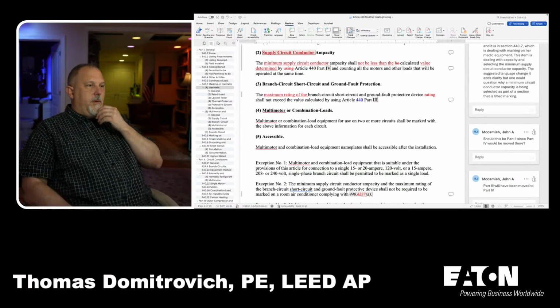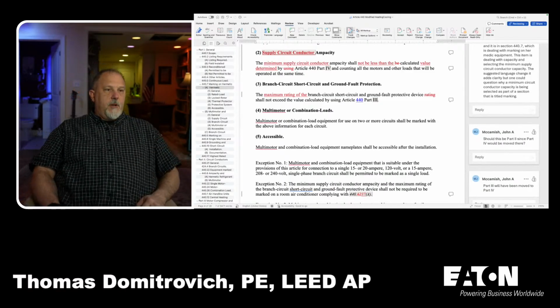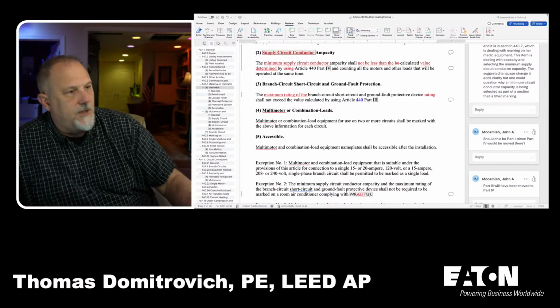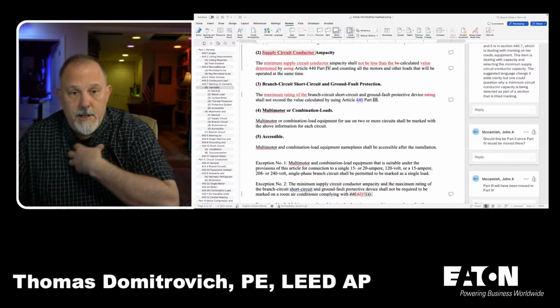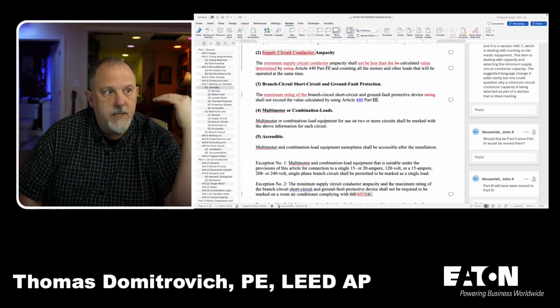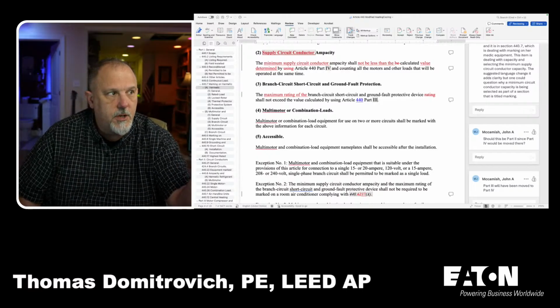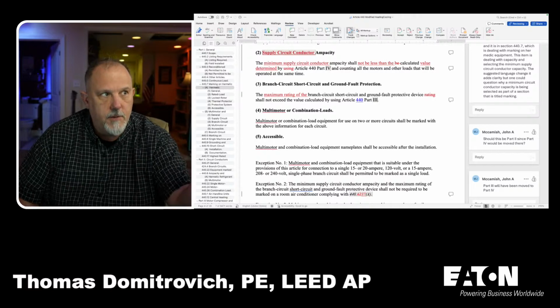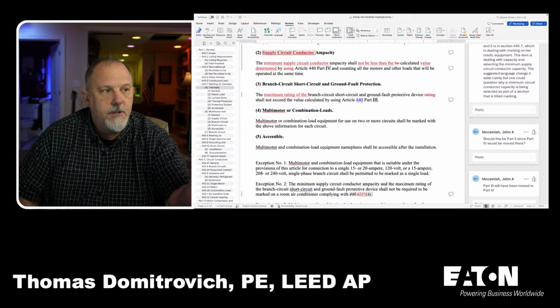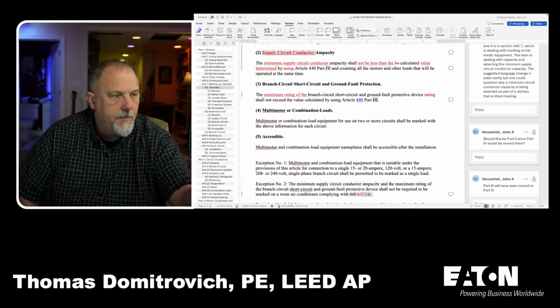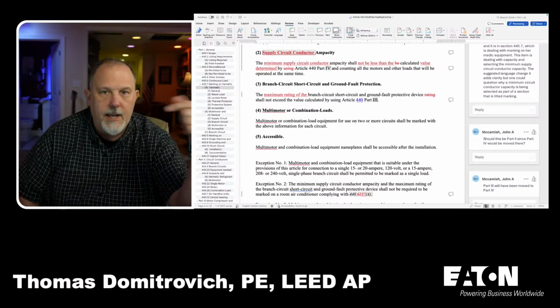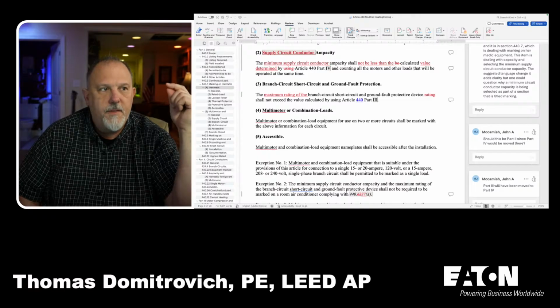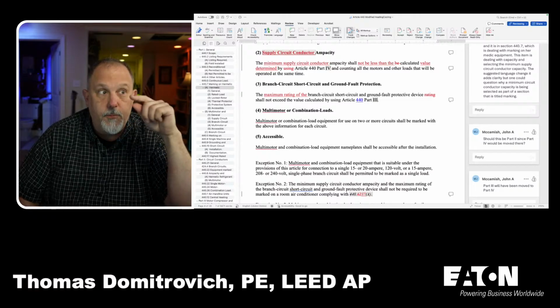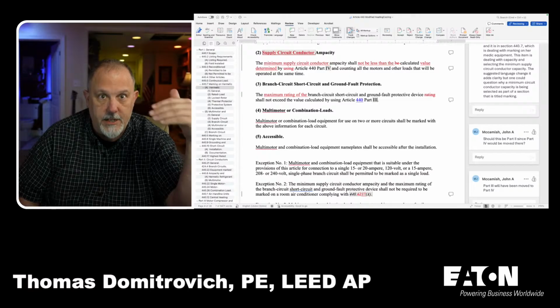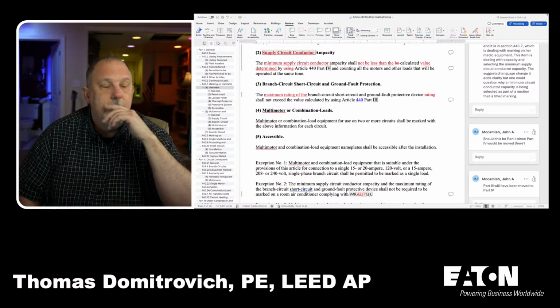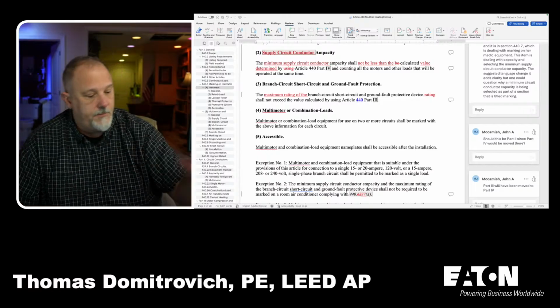Multi-motor or combination load equipment for use on 2 or more circuits shall be marked with the above information for each circuit. So in my opinion, there should be a section in here that says, here's how you determine the branch circuit, short circuit, and ground fault protection. Here's how you determine the ampacity of the conductor. Here's how you deal with whatever. And then you say it shall be marked with the following, and you list it, and you can put the references for each section where you're getting the information. That's not what they did here, and I'm not going to try to fix that.